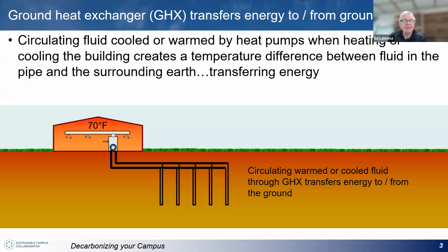So what we're doing is changing the temperature of the earth around the pipes. And that's the big advantage: you've got a lot of mass that you're taking heat from or dumping heat into. It takes a lot of energy to change that. It also means that you need to know how much heat you need for heating the building, or how much cooling you need, how much heat you need to get rid of when you're cooling the building. So you also have to know what the capability of the soil and rock is to absorb that heat or to give up that heat. So there's a lot of calculations to that.